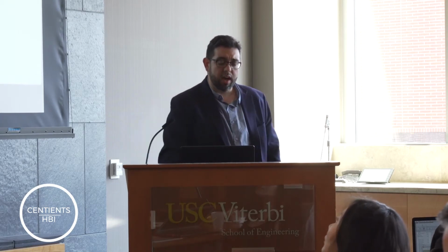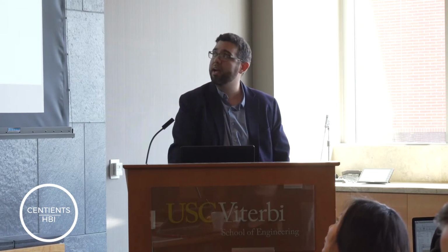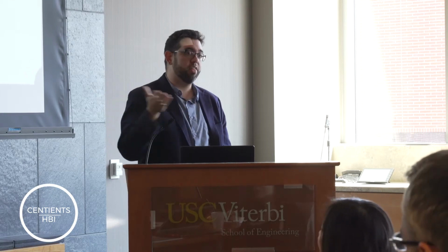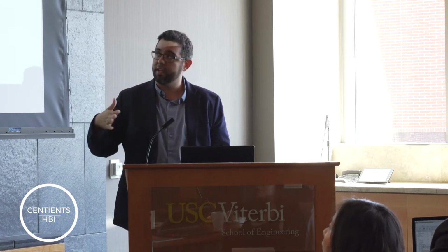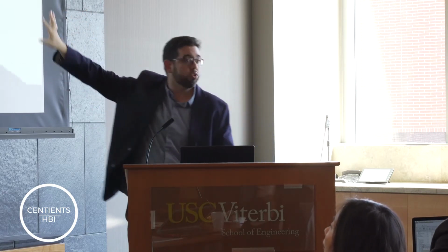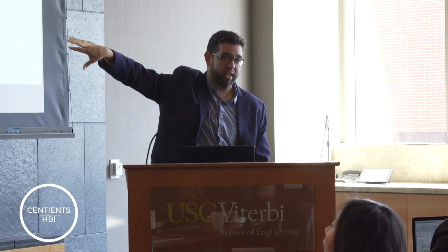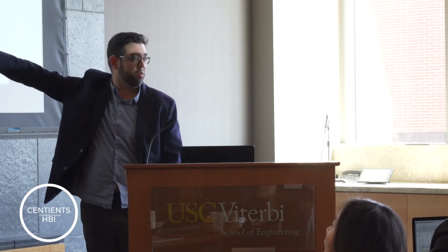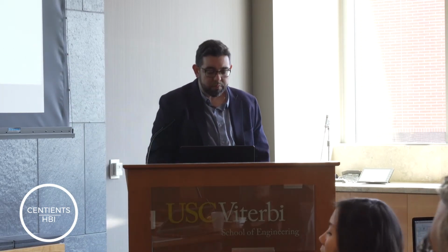And we actually ran this on several buildings. There was one building at the University of Tokyo a few years back where we found the AC being left on all night. Again, these algorithms know nothing about building systems. They're just doing this signal processing and correlation analysis. We found lights being left on all night. And we found simple changes in behavior that were anomalous only because we didn't incorporate weather data. So in this case, it may have just been a cooler day, which is why the AC wasn't left on, but it was still flagged, and this is presented to the building manager.